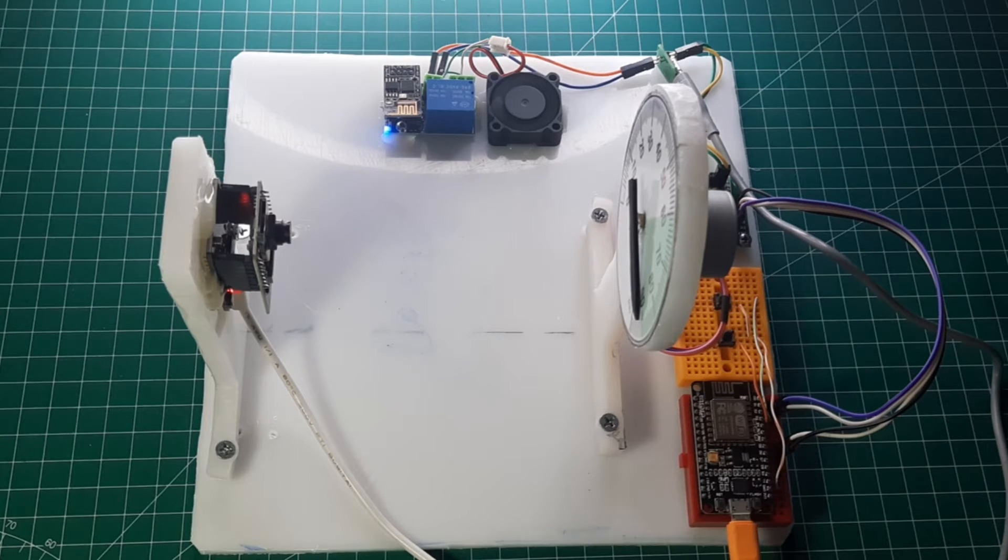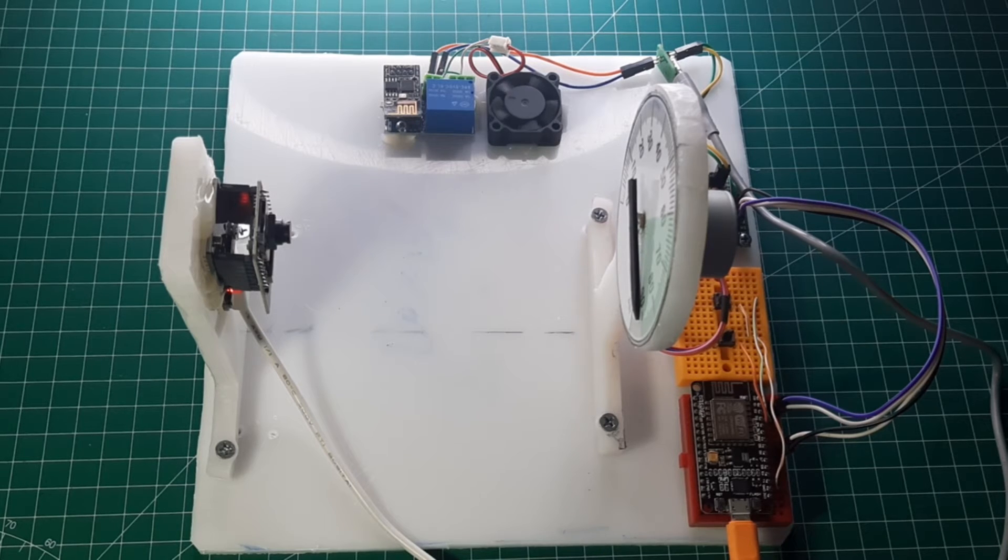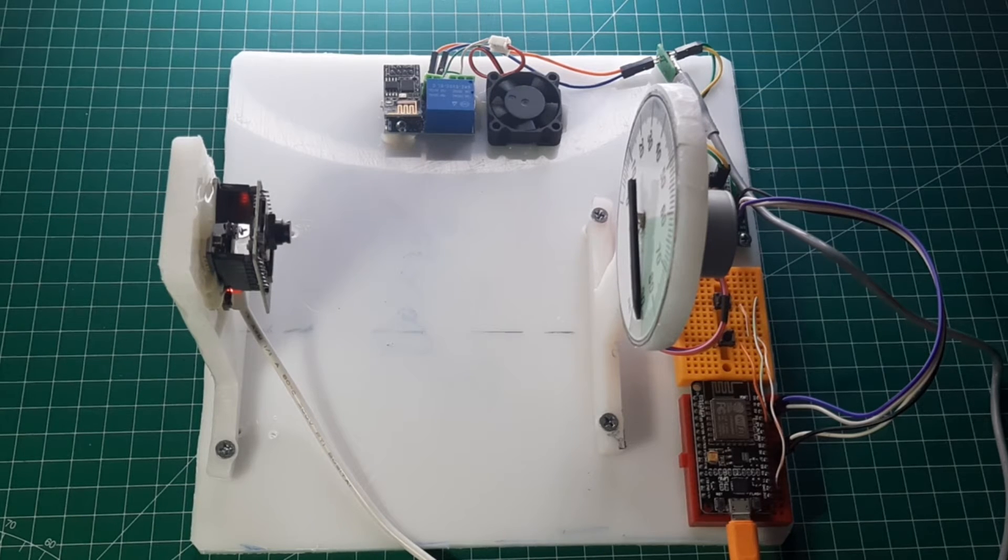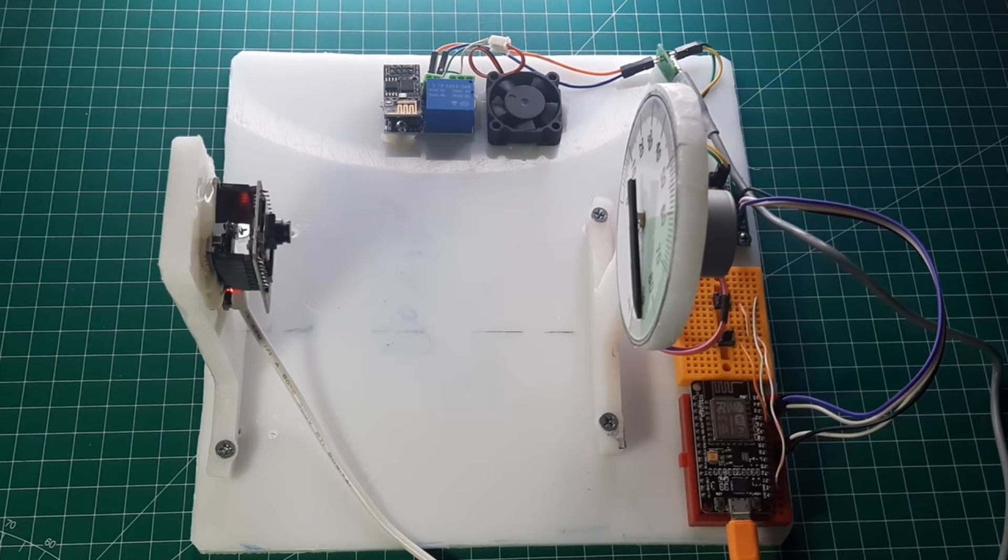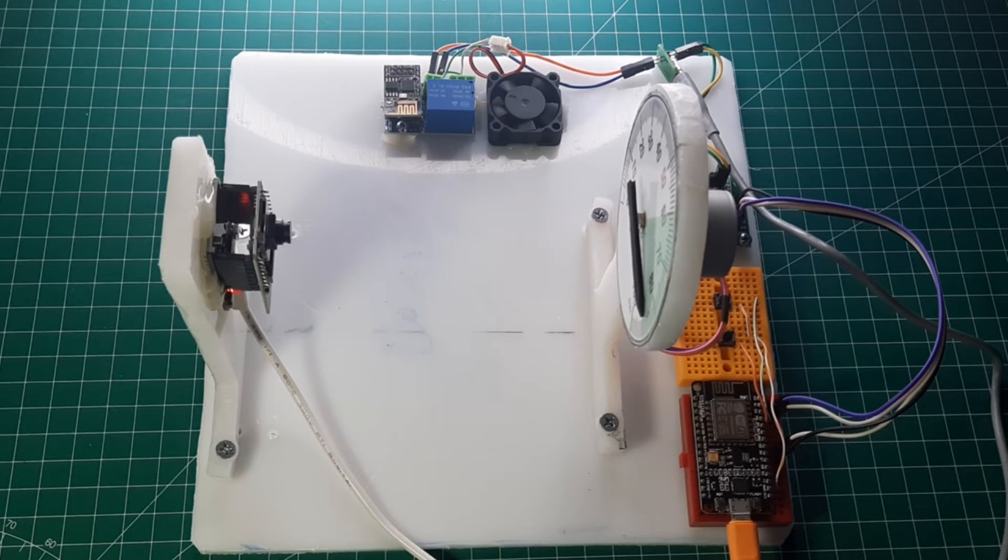After reaching the maximum pressure value that has been determined, the compressor will turn off. We can see that the fan as a compressor simulator has stopped rotating. Then the pressure value will slowly decrease due to consumption of pressured air.